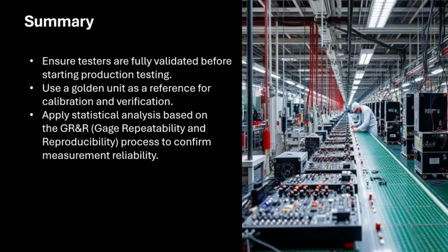After calibration, use a golden unit to verify that your tester is ready. Check every parameter. It might deviate by a certain amount, like let's say today when you measure the S21 for this device the result is minus 18, but tomorrow you get minus 17.9. That 0.1 dB matters for your specification and your tolerance. These are the things that you have to predetermine: how much is too much. Then you apply statistical analysis based on the GR&R process to confirm the measurement's reliability and also your tester readiness. You can apply this golden unit concept to the process. You can always check with the AI machine on what is the latest practice. I hope this helped. If you have any comments, just leave them in the comment section. Thanks for your time.